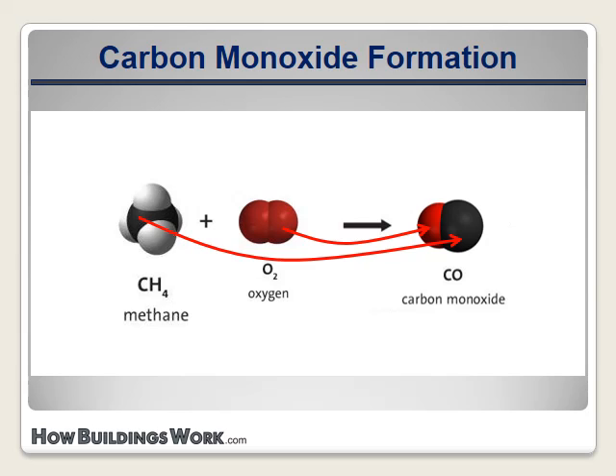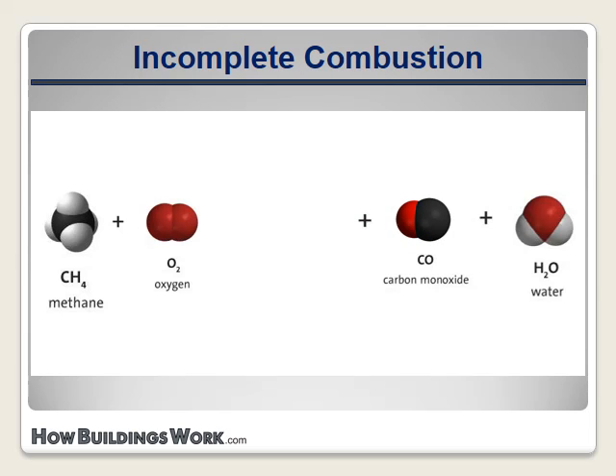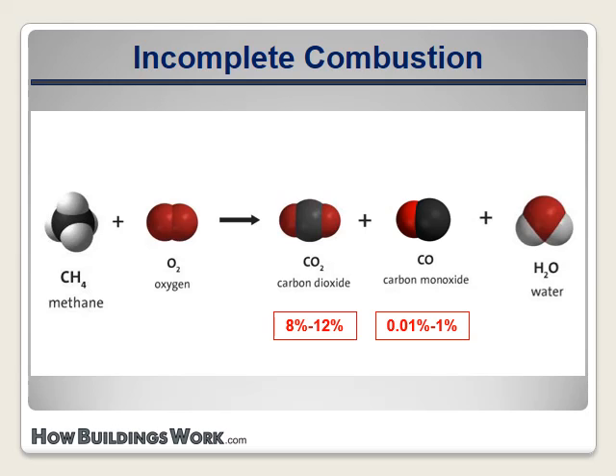The resulting compound is called carbon monoxide, with 'mono' meaning one. There are numerous reasons this can occur. Most often it's due to a fuel-air mixture that is rich, meaning that there's too much fuel and too little air. It can also happen when the flames are too cool, making it hard for the second oxygen to bond to the carbon. We'll cover these mechanisms in more detail in a later lesson. Whatever the cause, generation of carbon monoxide can present a serious health hazard and it should be avoided both in the design and the setup of combustion equipment. The reality is that a flame never generates just carbon monoxide—it always generates mostly carbon dioxide. Sometimes it generates no carbon monoxide at all. Sometimes it just generates a trace amount. But if the carbon monoxide levels get elevated to around 0.01% or more, we consider it significant and call the reaction incomplete combustion.